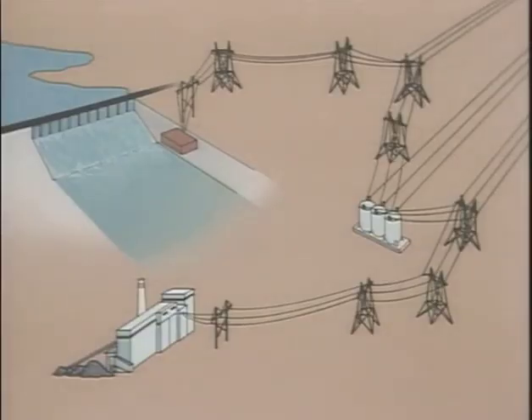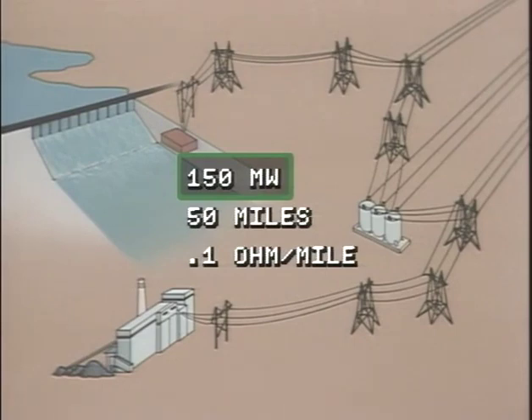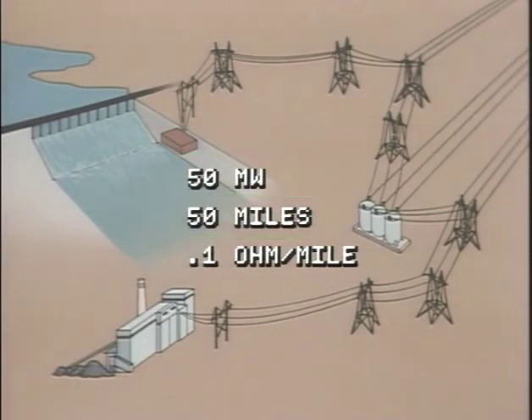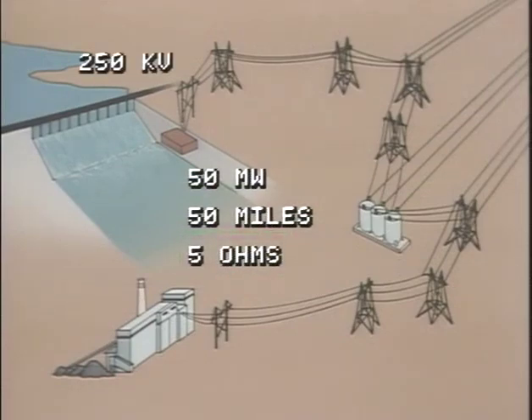This illustration represents our two transmission systems. Each power plant generates 150 megawatts of power. For simplicity, we'll consider one specific point in time when the power in each phase is 50 megawatts. Both systems run for 50 miles and each phase has a resistance of 0.1 ohm per mile, which totals 5 ohms of resistance per phase. One system has an applied voltage of 250 kilovolts and the other has an applied voltage of 500 kilovolts.